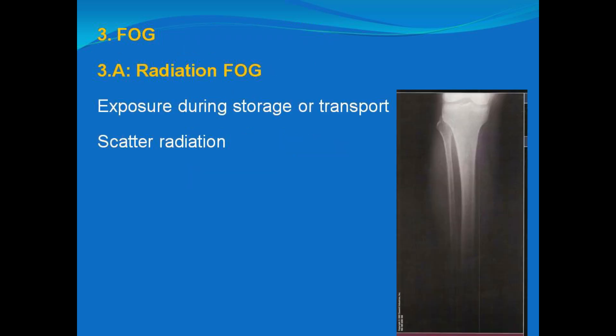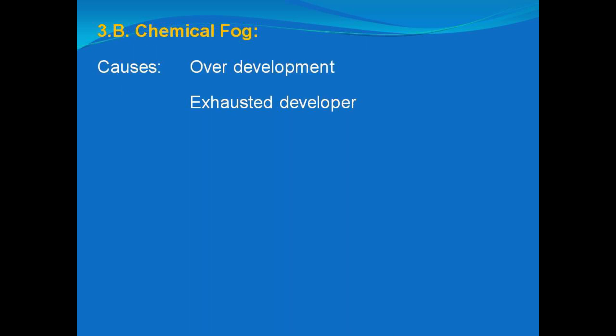Next is the problem of fog. Radiation fog is caused by exposure of the film to radiation — it can occur during transport of the film or due to scattered radiation reaching over the film, resulting in a non-clear radiograph.